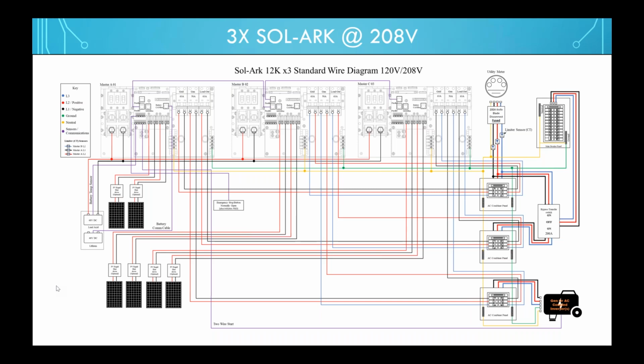So let's look at a battery backup. Why would somebody want battery backup? If you're a pharmacy and the grid goes down, you have high value inventory that is thermally sensitive. You have to keep your medicine cold. If the medicine's not cold, it goes out of spec for more than 5 minutes. You have to throw it away. Highly regulated by the FDA, high value inventory that needs to be kept refrigerated. So as far as I'm concerned, every pharmacy in North America, every pharmacy in Canada and the United States needs battery backup. They're all going to be 208 volt 3-phase.